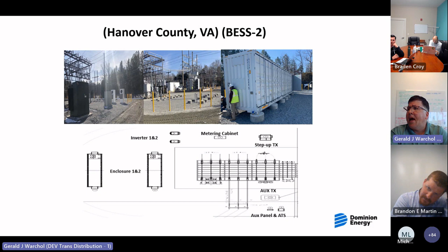So let's talk a little bit more about shifting transformer load and what that's all about. We call this a non-wires alternative solution, right? So what we do is we take a transformer and put a battery just downstream of it. This is a distribution transformer that's pulling power off of the bulk electric system, and we are trying to charge that battery during low peak and then discharge during high peak.